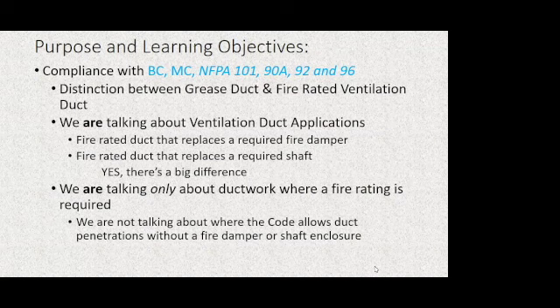So we are talking about those fire-rated duct products that are applied as a substitute for fire resistance that's in the code. That might come from a requirement that stipulates the need for a fire damper in an HVAC system, or the need for a shaft with fire resistance to protect an HVAC system. So we're dealing mostly with life safety applications, and that's where we're going to find most of the criteria, the code paths, coming back to the fire resistance that's prescriptively called out in the code. We are talking only about the ductwork that is specified in the code for that fire resistance.